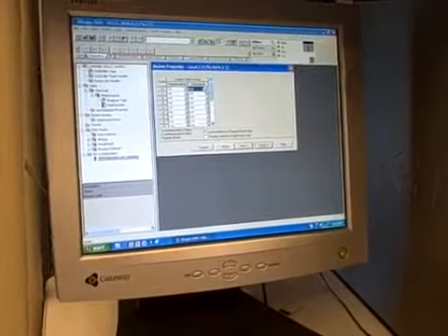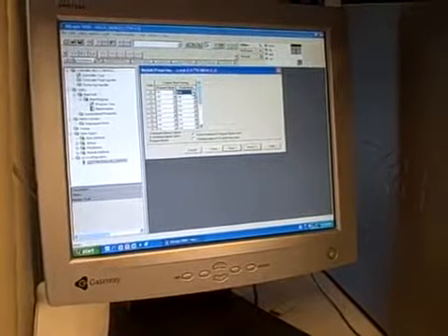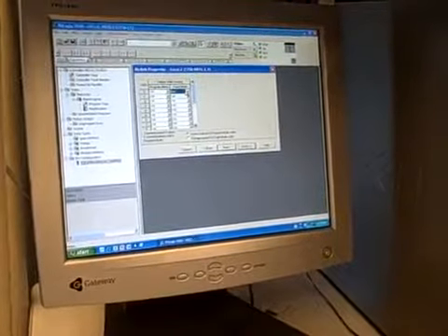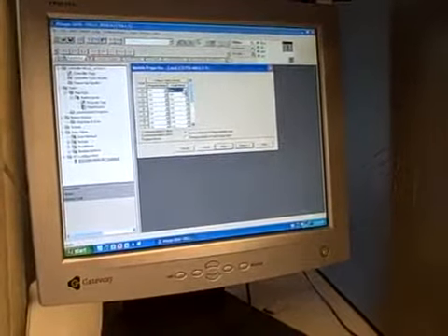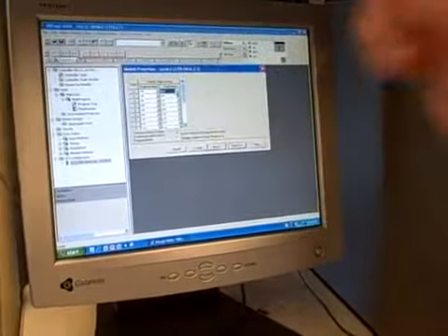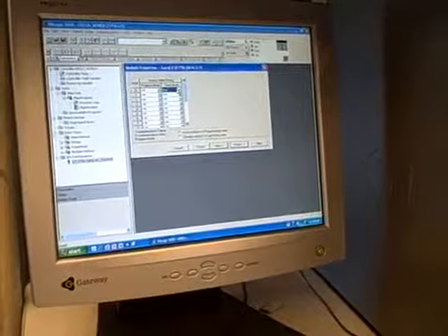However, if I want to, I can tell them to hold their last state or to go on. This could be important, I should say it is important for safety. If your machine is being controlled or your process is being controlled by a PLC, you want to be able to specify what those I/O channels will do in the event of a program mode switch or a fault detected.